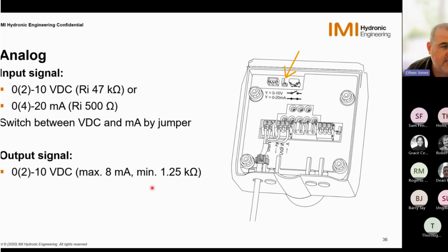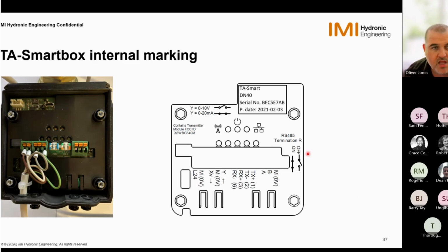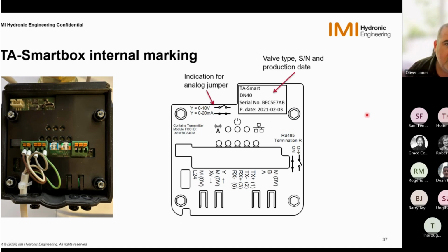And then, as I say, our output signal is 0 to 10 volt, 0 to 10 VDC only. The markings internally, as I say, there's the analog jumper, and this is the indication for it, which typically would sit here on the inside of the box. So what you can see on this diagram would physically be printed onto the plastic of the smart box. This is probably one of the early development units that was used to photograph at the time. We then have the valve type, so our serial number, production date, what size the valve is.